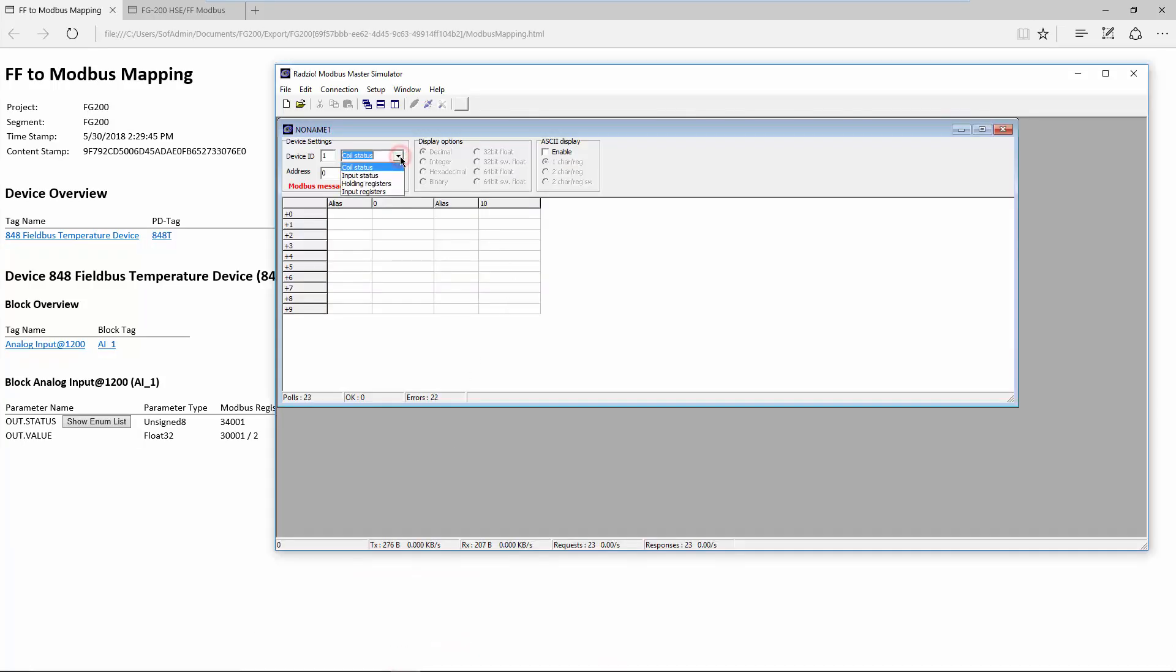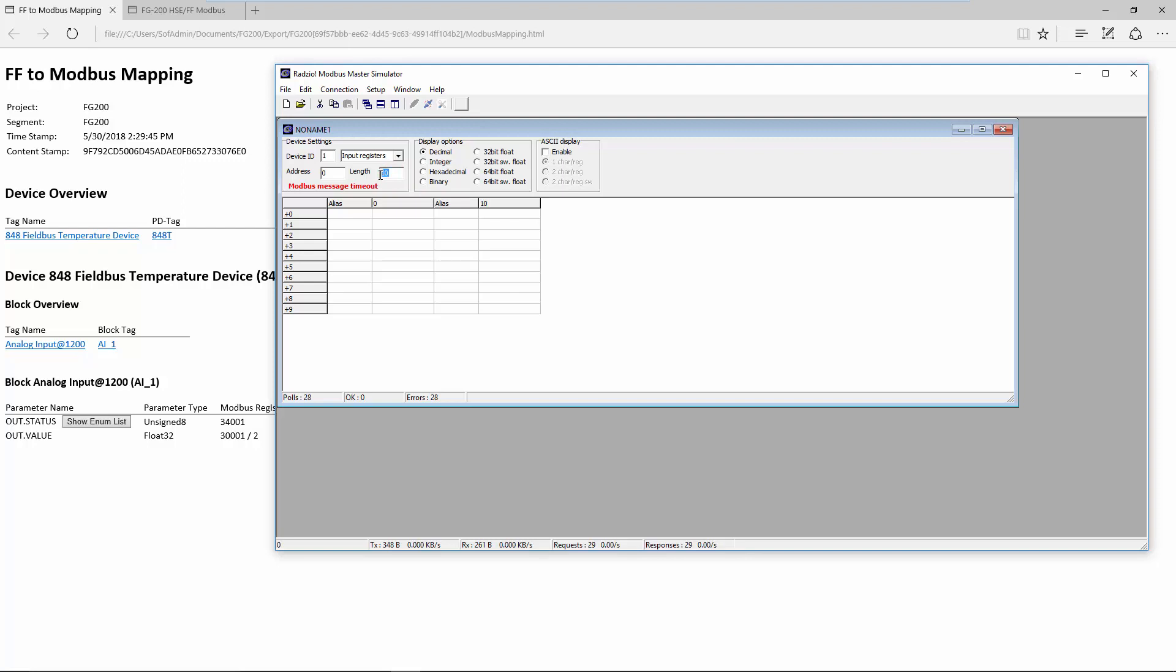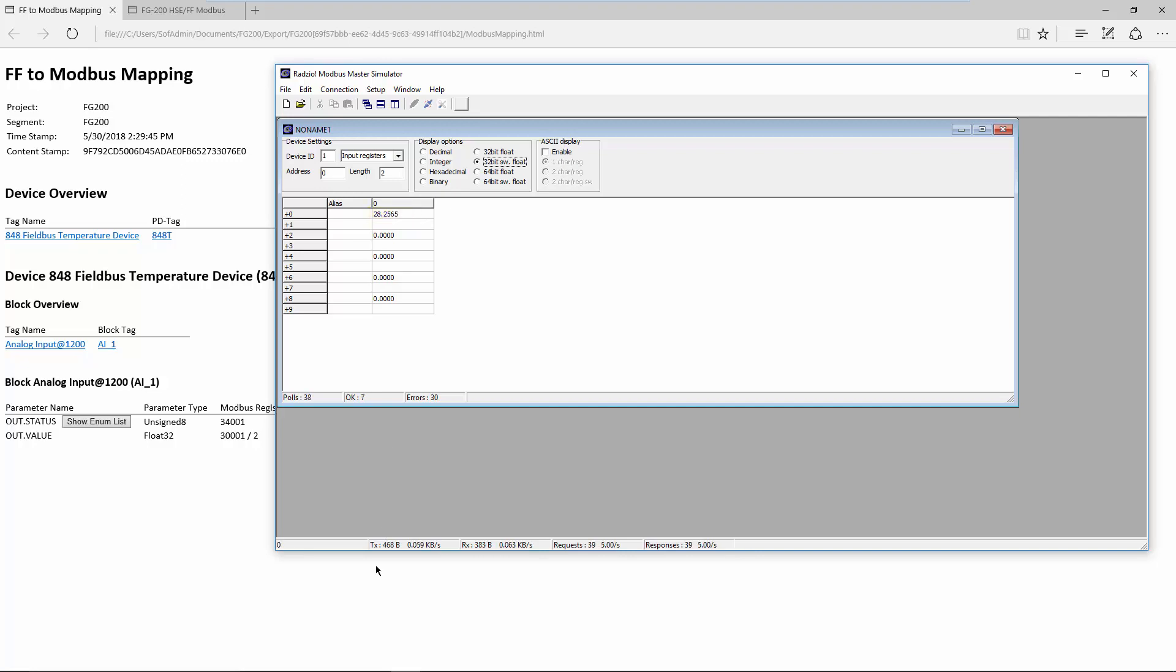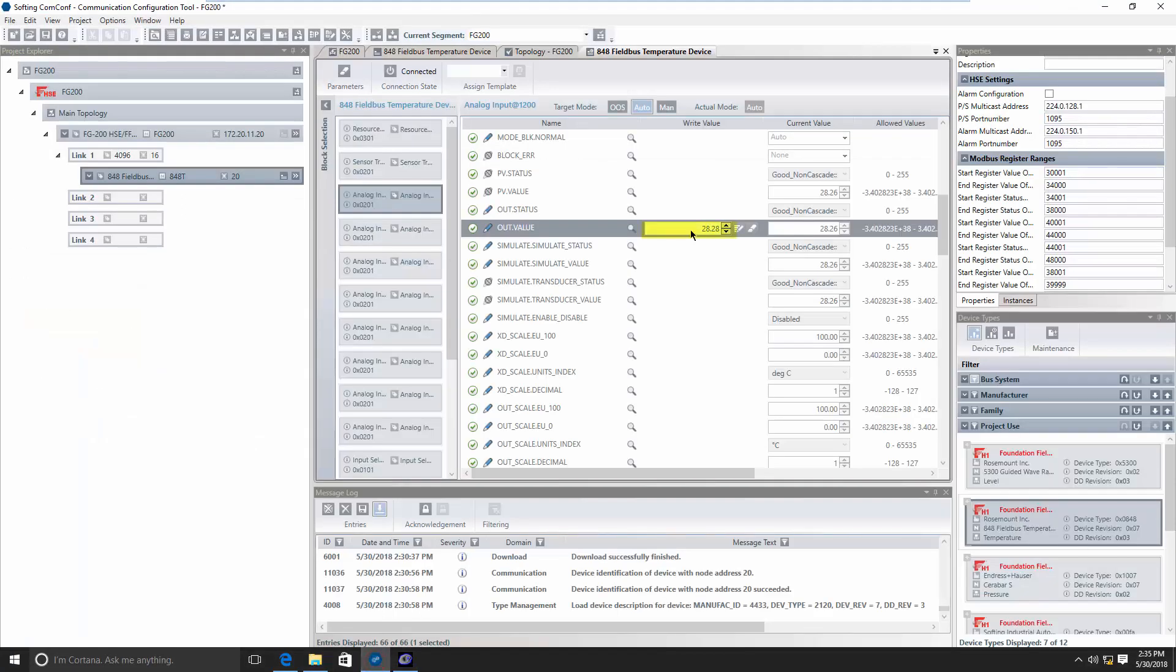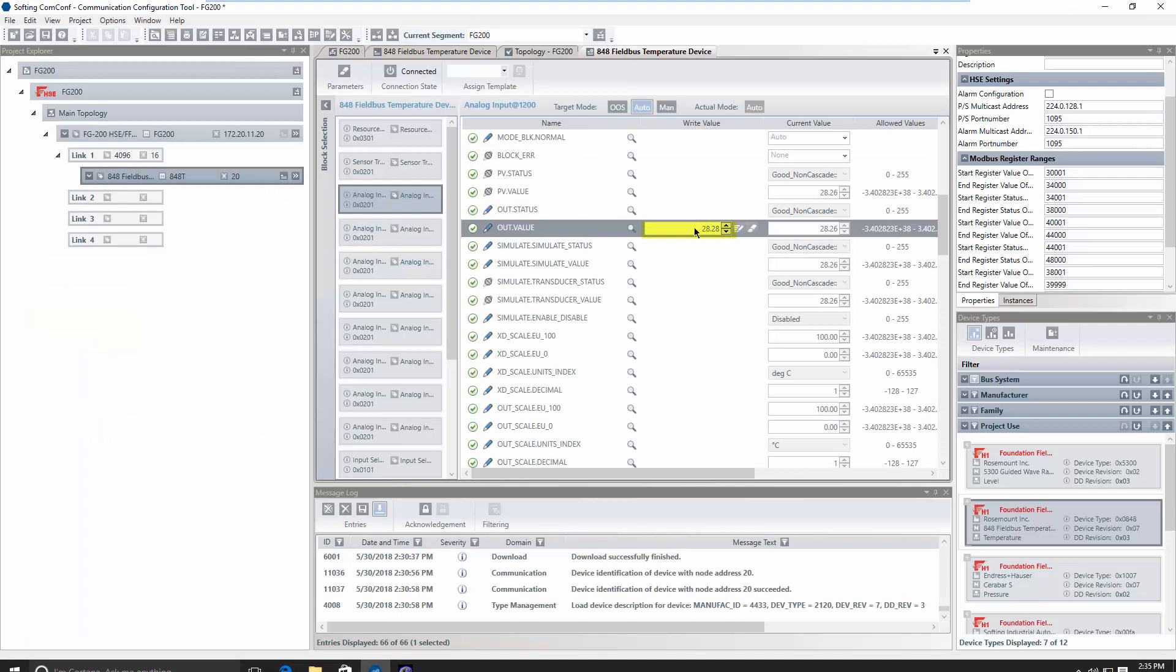Select input register. In the address field, you have to define the offset to 30001. For the process value, this is 0. So, you don't have to adapt the address. Adapt the length to 2 because the process value uses 2 registers. Adapt the display options to see the value in a proper format. The value matches the value read from the device in the communication configurator.